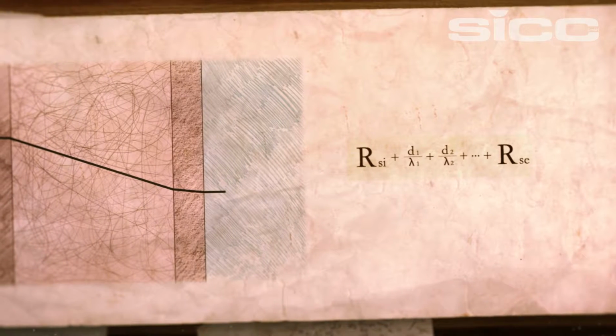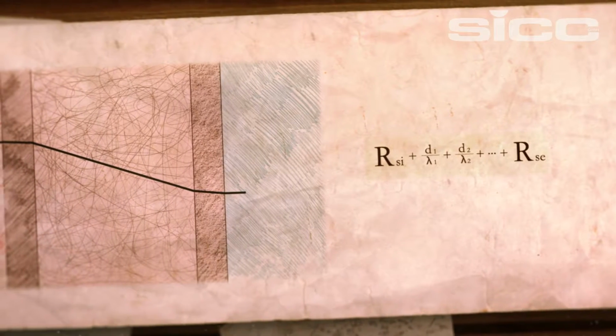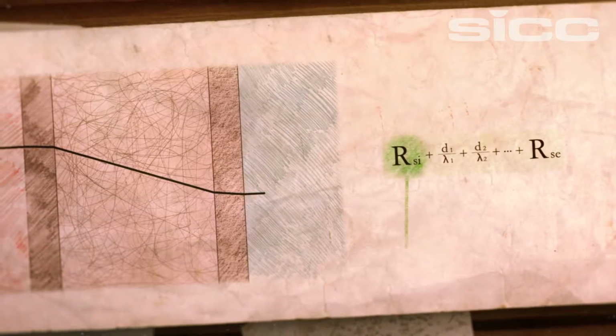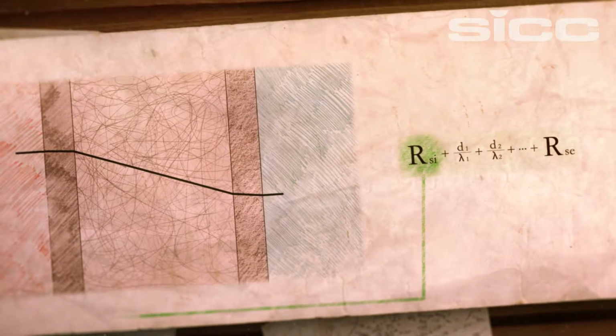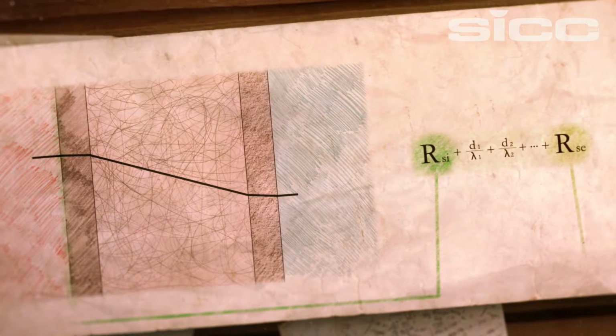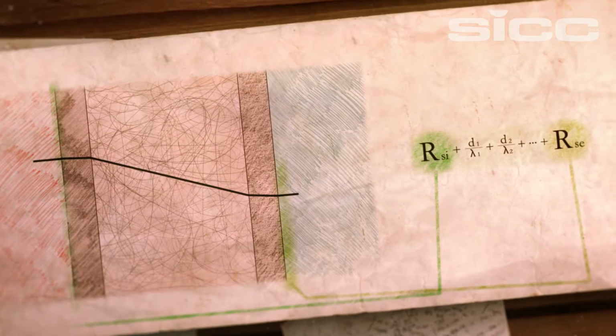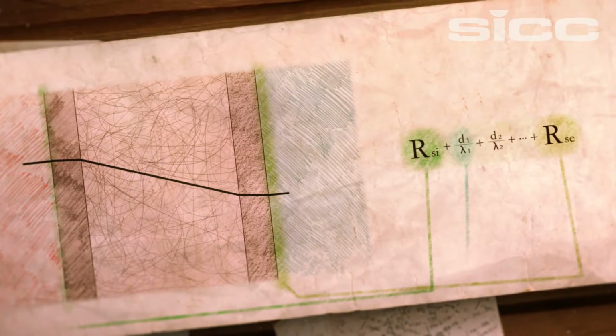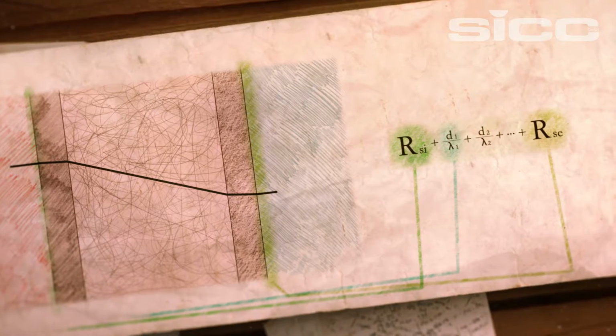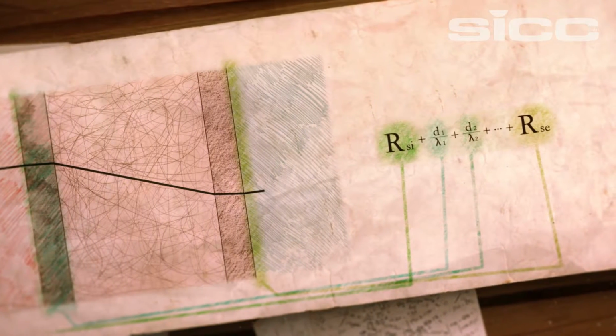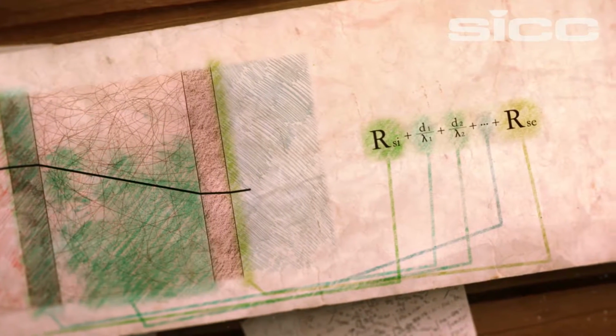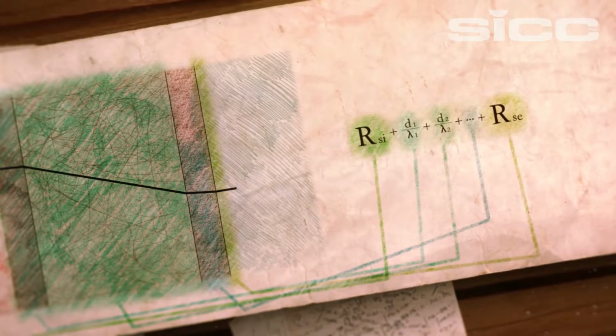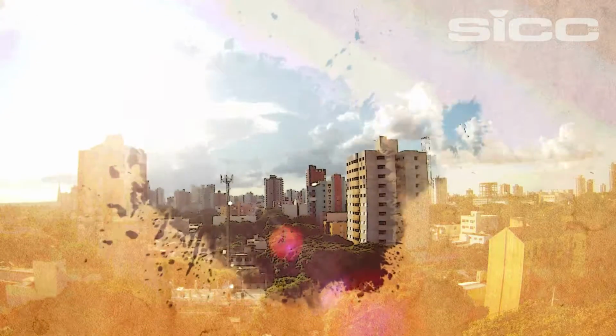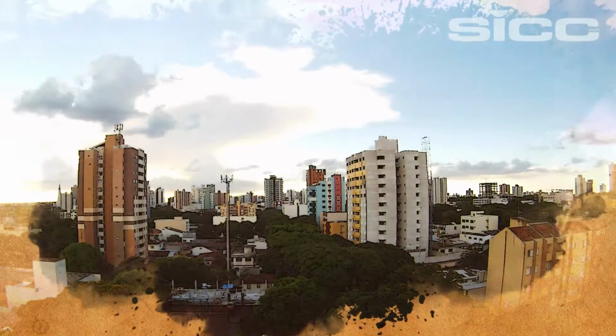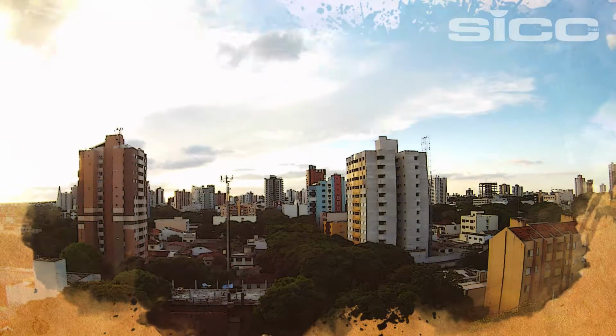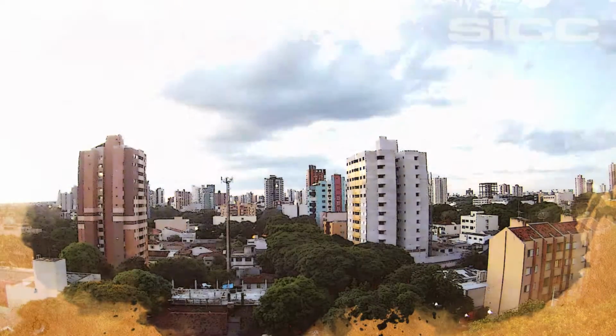This heat transfer coefficient of the wall is built up by the resistance of both inside and outside. Of course, they are DIN standardized, and they are marked as Rsi and Rse. The wall consists of independent layers of construction material which are specified by their thickness and value of heat conduction. For most buildings without insulation, U-values of 1.2 are known.